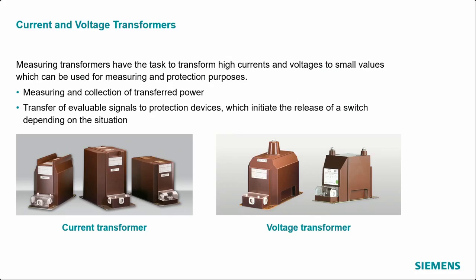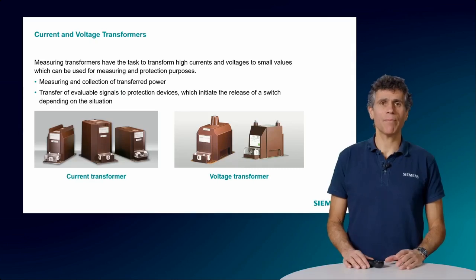And finally, the last two components, the current and voltage transformers. They have the task to transform high currents and voltages into small values, which are used for measuring and protection purposes. Transformers provide a scaled-down replica of the voltage or current in the power system, keeping the phase angle approximately the same, which is crucial for certain measurements and protection schemes. These components provide a way of safely observing voltage and current without interfacing directly with the high currents and voltages involved. There are several types of devices that can perform this task.